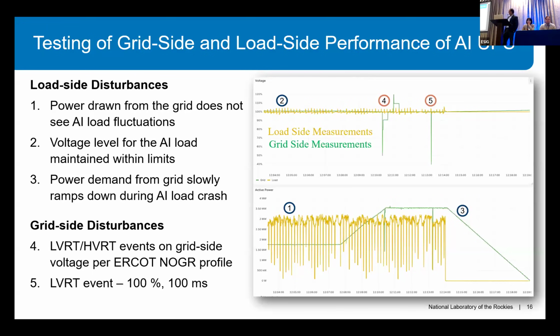Starting here, we are running a particular AI load profile, and as you can see on the load side, we are feeding that load, but on the grid side, the power remains flat. So the AI load fluctuations don't transition to the grid side. Of course, there is a change in the power that we draw from the grid to make sure we are meeting the load demand, but the ramp rates are limited based on the requirements set by the grid operator.